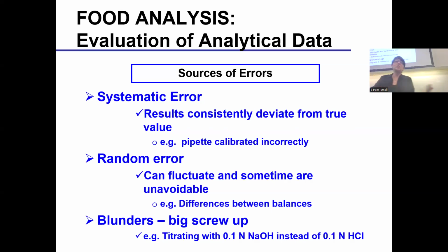You're doing the experiment, you're doing everything right, but something is really messing you up. Let's say the spectrophotometer that you're working on, the bulb is dying. So all your absorbances are really low because the intensity of the light is low. That has to do with the instrument.